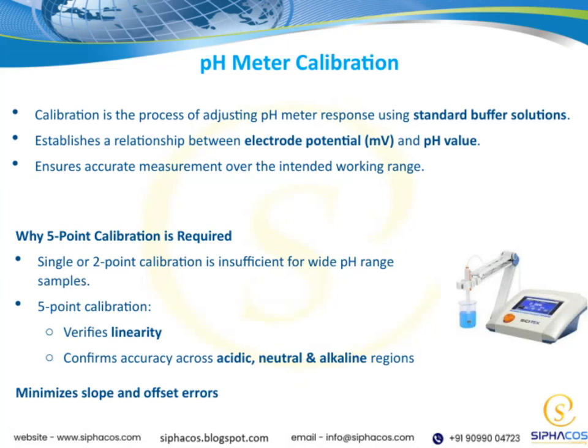Let's talk about why a 5-point calibration is necessary. Using just a single or even 2-point calibration simply isn't enough when you're working with samples that cover a wide pH range. A 5-point calibration helps verify the linearity of your pH meter, ensuring that the response is consistent across different pH levels. It also confirms the accuracy of your measurements in the acidic, neutral, and alkaline regions, so you're confident in your results no matter where your sample falls. Another crucial benefit is that it minimizes slope and offset errors, which can otherwise lead to inaccurate readings.